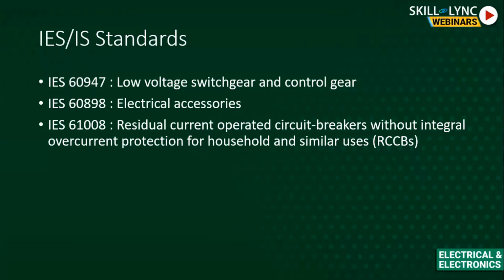Wherever your product is supposed to be used, you must comply with those standards. So if you are selling in India, you must comply with the Indian standards. If you are selling in some other geographical location, you must comply with those standards. So if we talk about IEC 60947, that covers low voltage switchgear and control gear. So if your product falls under this application, you must have compliance with this standard.